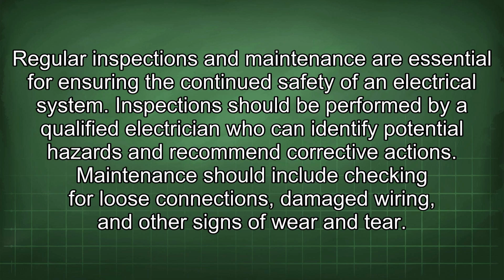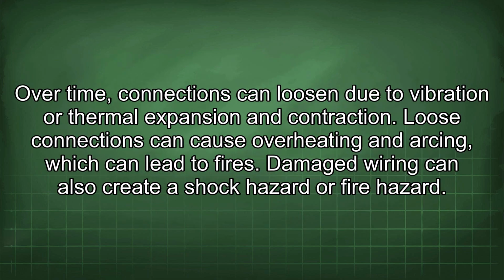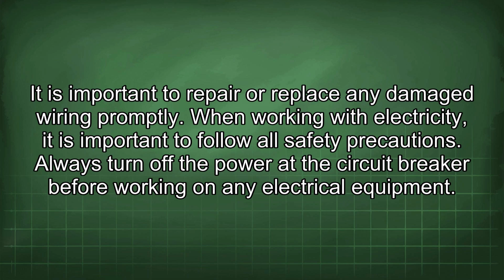Maintenance should include checking for loose connections, damaged wiring, and other signs of wear and tear. Over time, connections can loosen due to vibration or thermal expansion and contraction. These connections can cause overheating and arcing, which can lead to fires. Damaged wiring can also create a shock hazard or fire hazard. It is important to repair or replace any damaged wiring promptly.